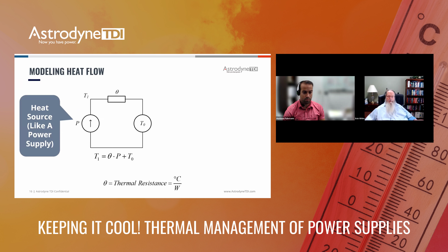So what is the heat flowing into? From that heat source, like a power supply operating and dissipating power internally, most often that T0 is the surrounding air, the ambient air. So T0 would be the ambient temperature. It's important that ambient temperature be recognized as the temperature right at the power supply. So if the power supply is in a box, it's the temperature in the box, not the temperature in the room. We'll talk more about that in a bit.